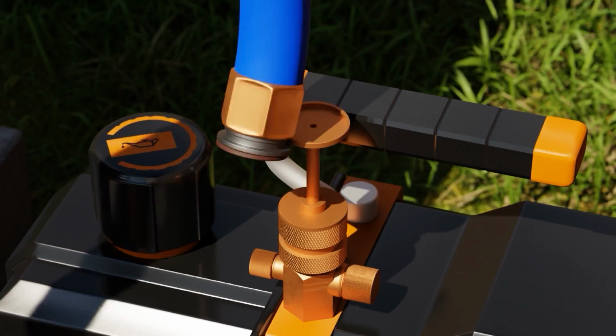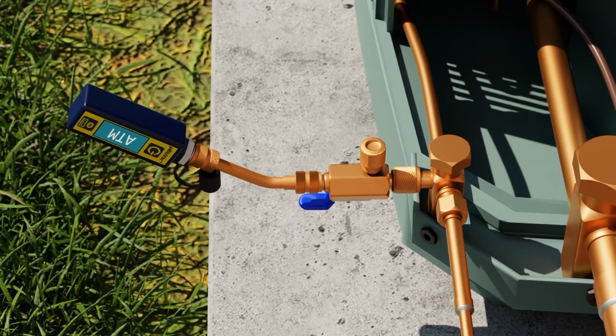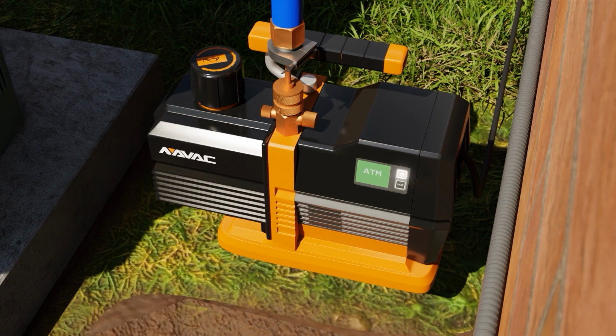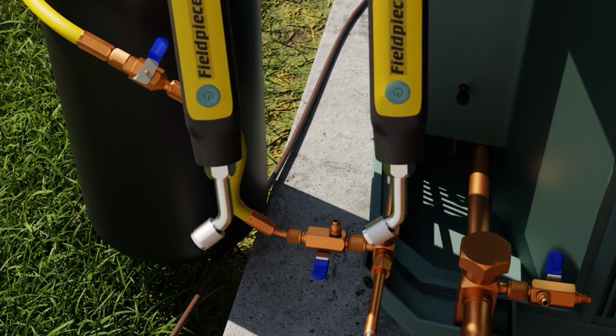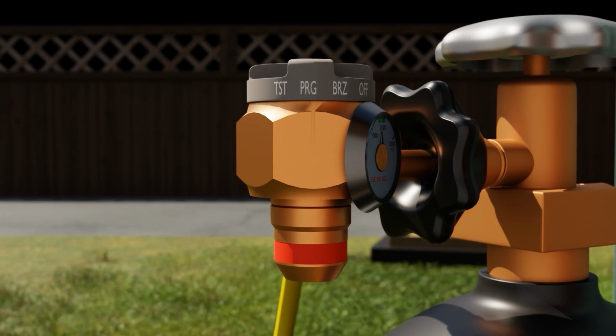The vacuum and the pressure testing is universal for all the systems that we work on, so we didn't develop a step-by-step slide for you guys on that. We have all of that in articles, videos, and HVAC school checklist, so you can check that out. But best vacuum practices are really important. People are buying these kits online sometimes and just hooking them up and putting them together and creating their own problems with their electronic expansion valves seizing up because there is moisture, there's crap inside the system. So a vacuum is still a really important step, and that decay test will also let you know. It can be your guarantee that there's no issue with your flare joints.